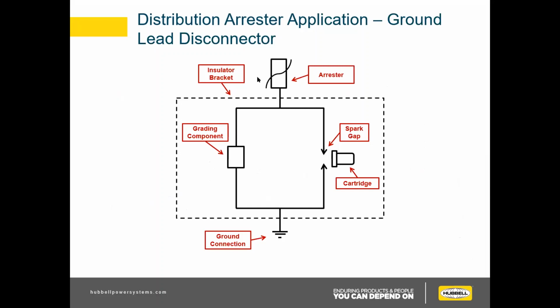And we'll go into a little bit more detail here about our ground lead disconnector. So in the box here, you have just the insulating bracket. You have your arrestor out here and your ground connection here. What happens is, the grading component conducts just those milliamps of current all day, every day.